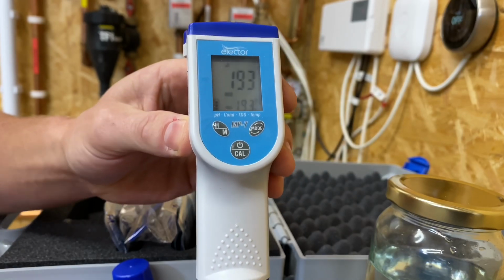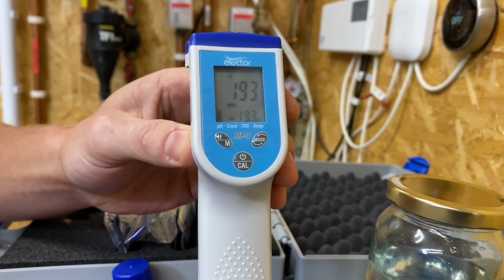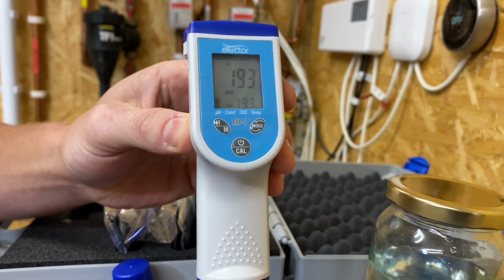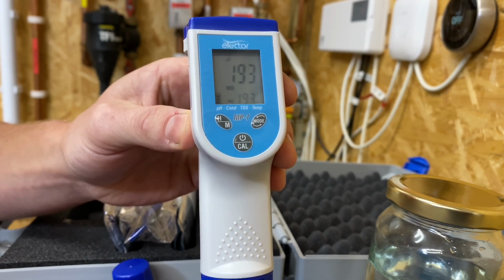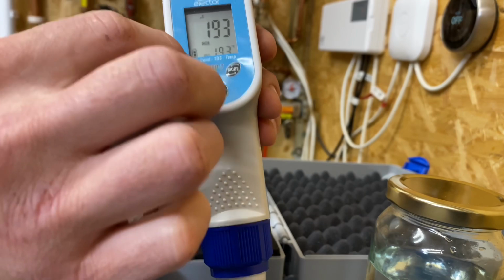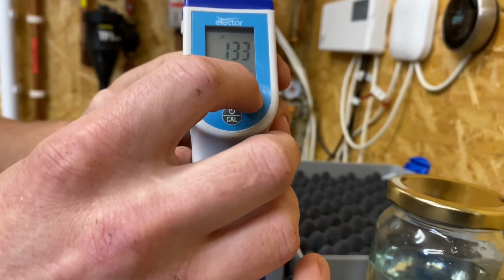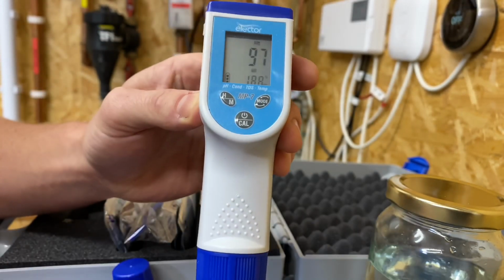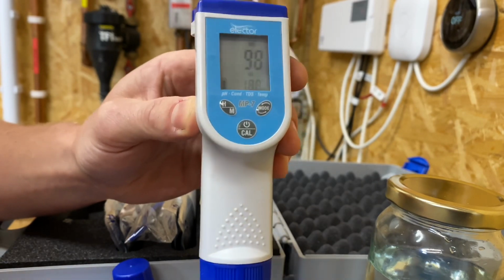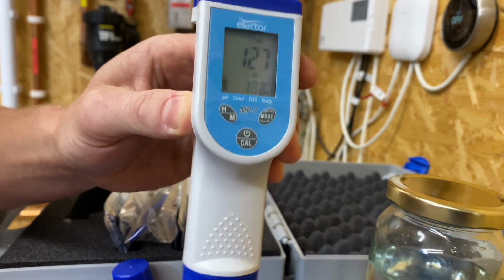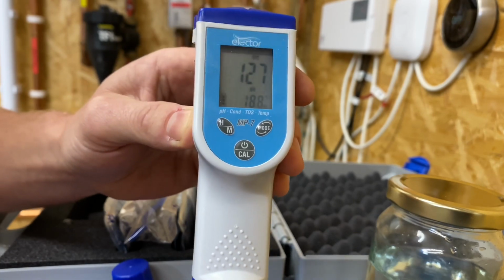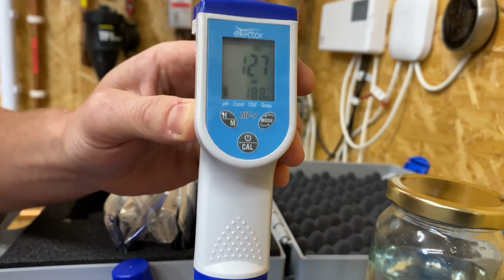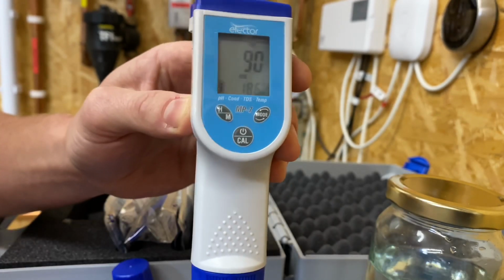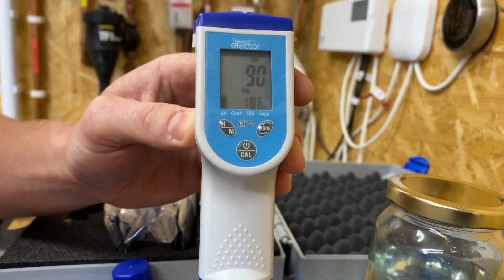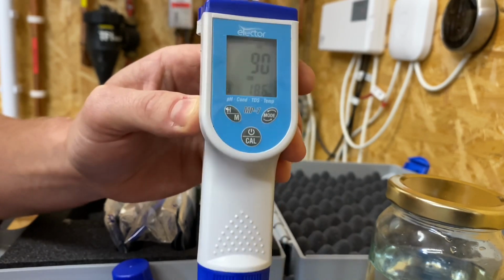So the incoming conductivity here is 193, so not particularly high, but still not within the limit of VDI, which is less than 100 microsiemens. And press the mode, and we've now switched to TDS. So this is measuring the total dissolved solids, about 127. And one more time, switch to the salts, so about 90 parts per million there.